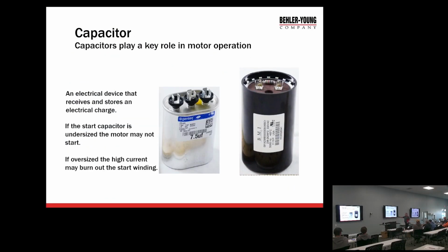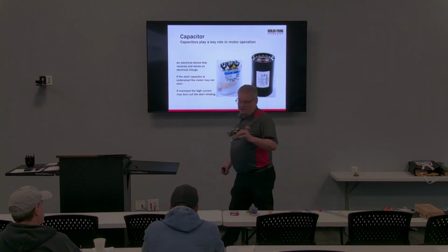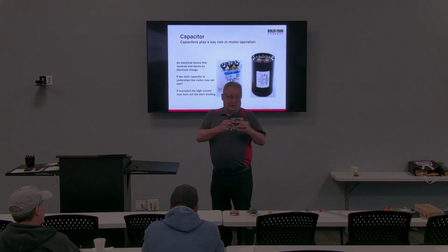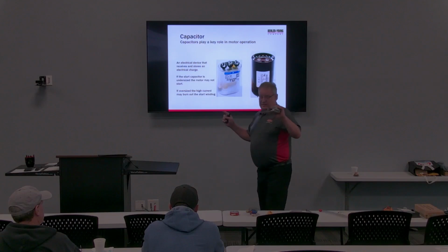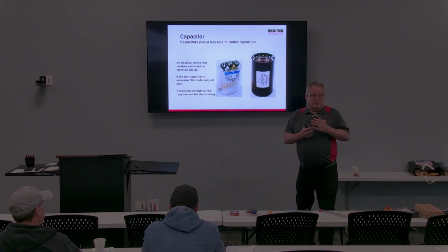The metal ones are run capacitors. The bakelite ones are start capacitors. They do hold a charge. Okay, so be aware of that. When we're dealing with circuit boards, this is actually a little inverter board for a condenser fan motor. These little guys will hold a charge just like those will. These are capacitors, same way. So when you're dealing with this, and we get more into inverter boards, these will hold up to 300 volts for up to 5 minutes.